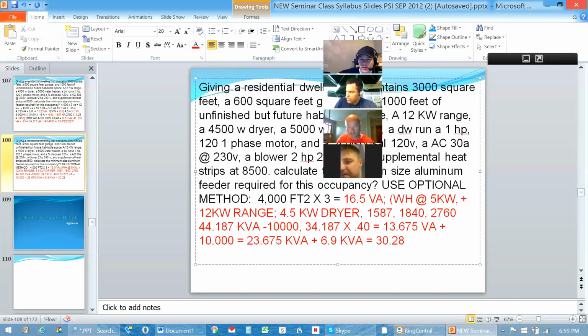34,115. Well, remember this 30.575 is going to be actually derated in the same manner. So I'm looking at 30.58 kVA. I'm going to take that 30.58 kVA and multiply it times the same 0.83. That doesn't really change between the different methods. And that's going to derate that value to 25.37 instead of the 34 that we had on the standard method. 25.37.